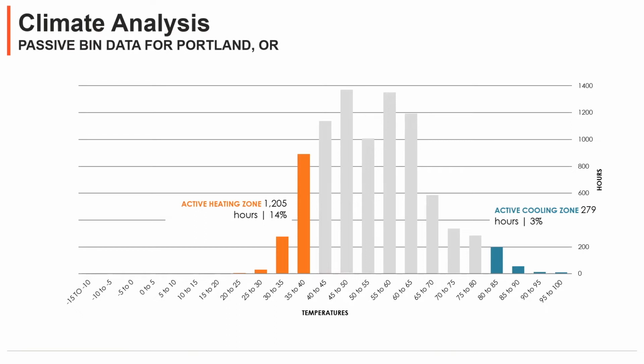And not having mechanical cooling is just like not having enough heating, say like a VRF system where you have to run it 24/7 to keep at 72. If you're east of the mountain range, you better have some way to reheat a building after, say, a power failure, or you'll never get the building back online in a few days. But anyways, they went through this and they talked with the district and they said, we love it, we love it, we love it. But we have to have mechanical cooling, at least in the classrooms, for where all of our teachers are.